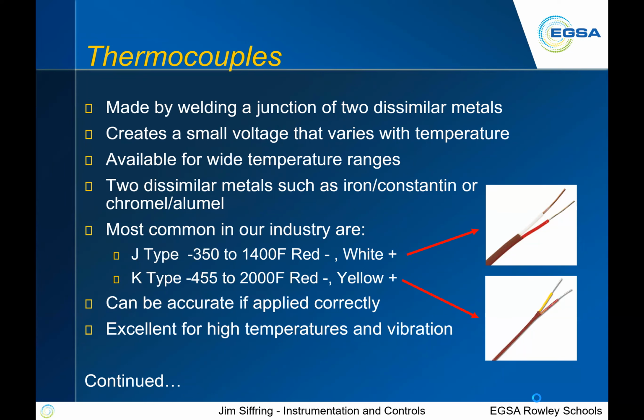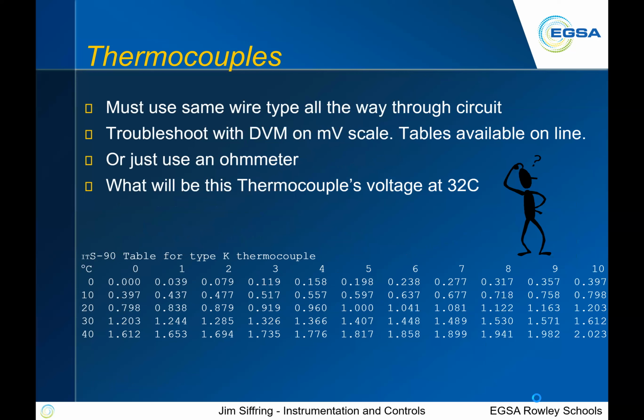Now, one thing to note, like on the J type, the red is the negative side, the white is the positive side. Similarly, the K type, red is negative, yellow is positive. That's different than most other DC wiring because red is typically a positive lead. White is often common. So keep track of that. That's an indication of what type of device it is, not necessarily what polarity and things like that are. Really good for high pressure, high temperature, high vibration type applications.